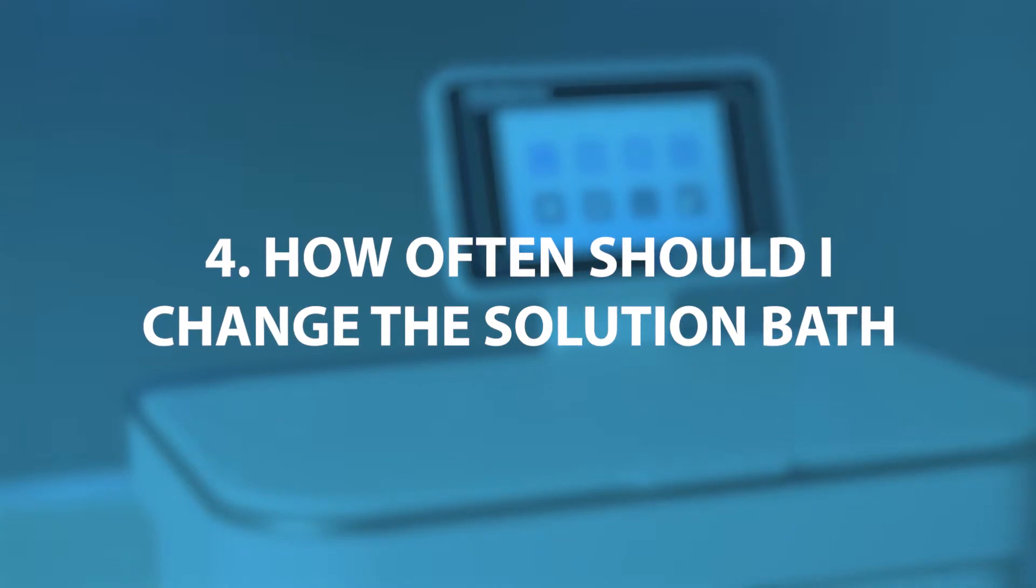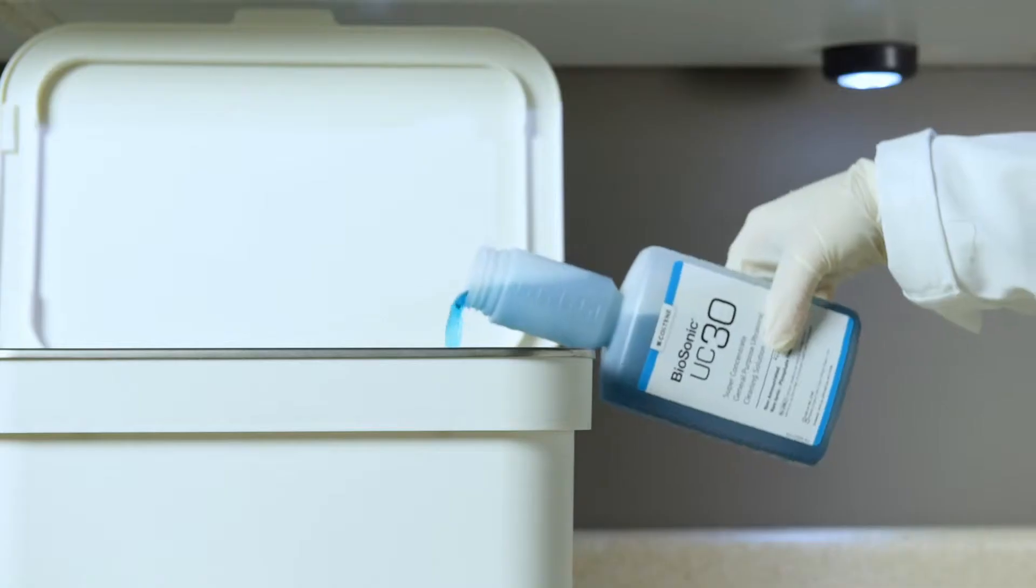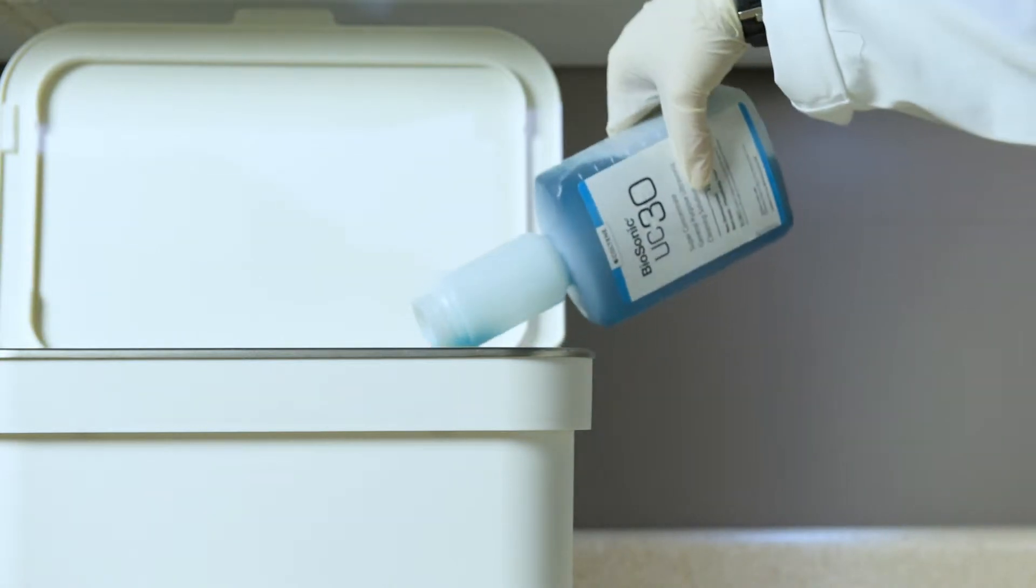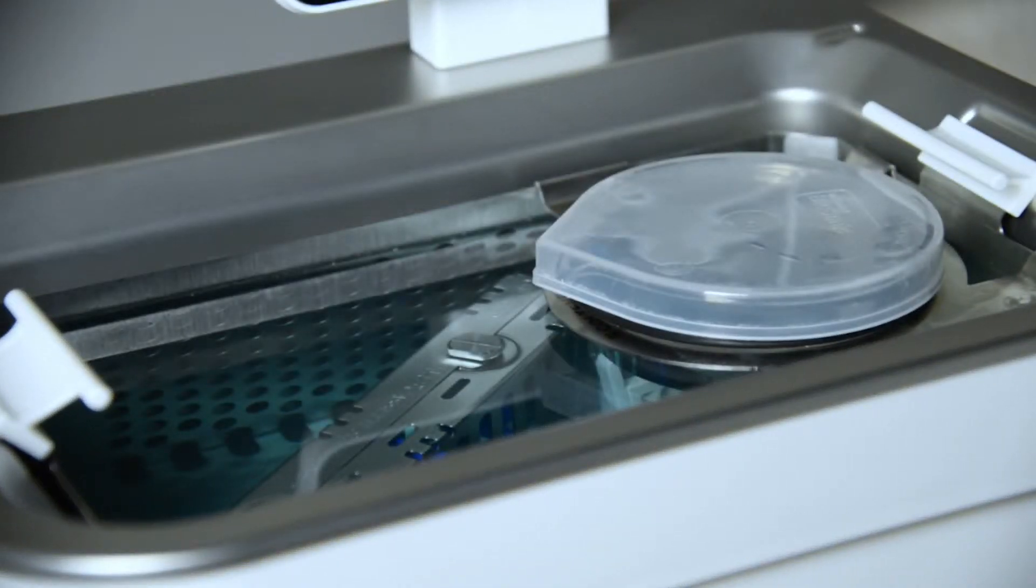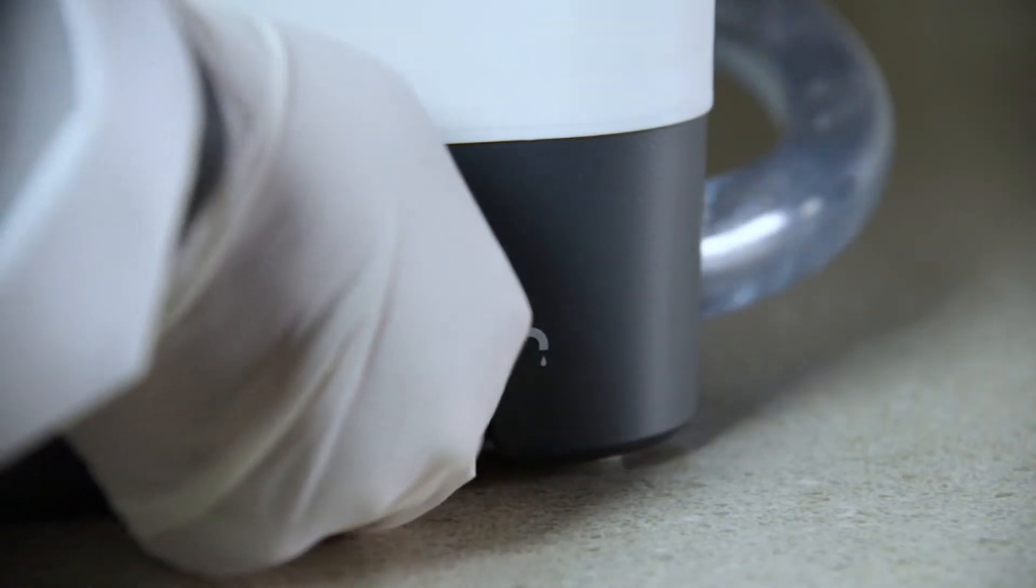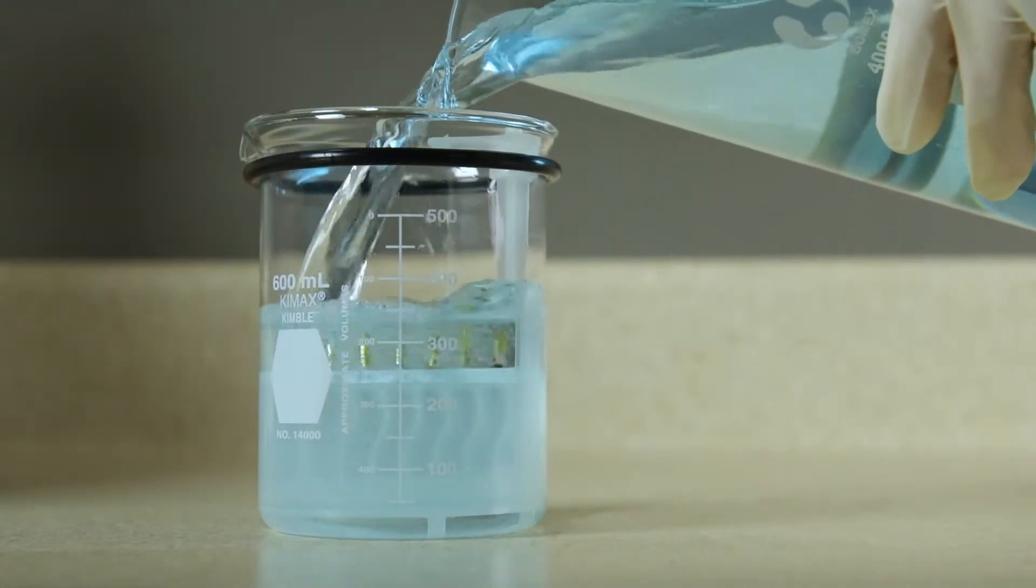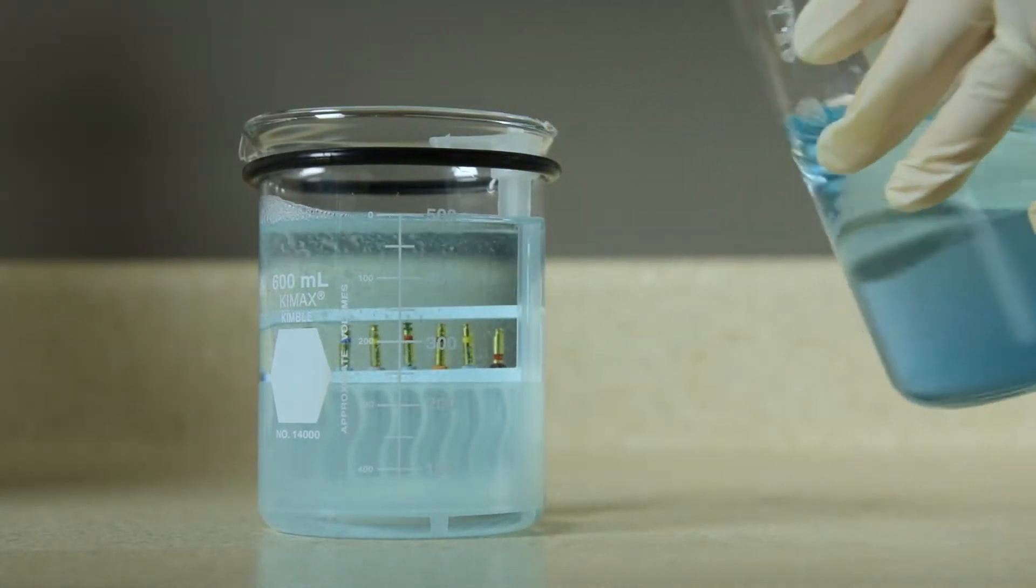How often should I change the solution bath? How often the solution bath is changed depends on the solution used, frequency of use, and size of cleaning loads. Changing your solution every eight hours at a minimum is recommended, or whenever the solution becomes visibly soiled or dirty. When beakers are used, change the solution in the beaker after each use.